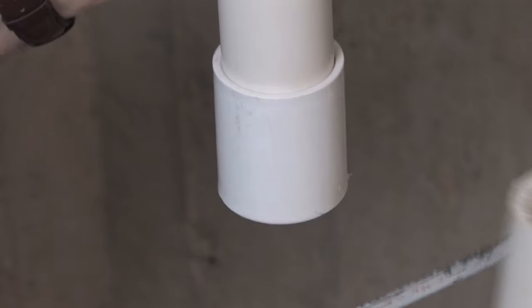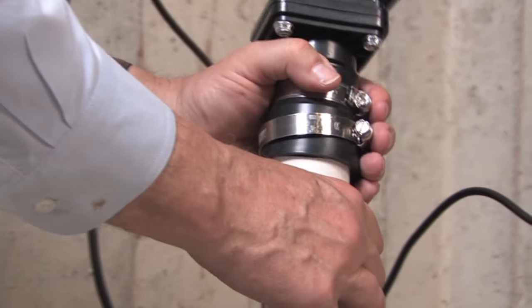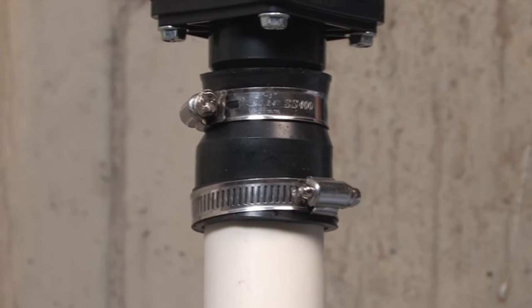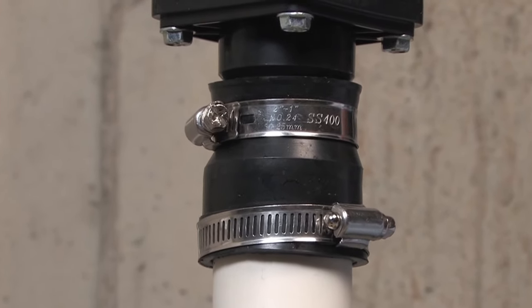Unplug the primary pump and cut the discharge pipe about one foot above the floor. Install a check valve on the top of the discharge pipe and tighten the bottom hose clamp. Make sure the arrow on the check valve is pointing up or it will not prevent the backflow of water.